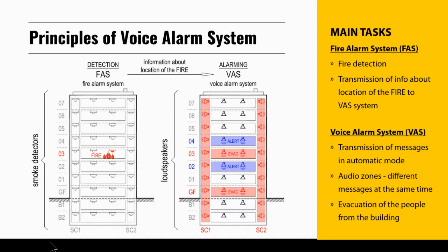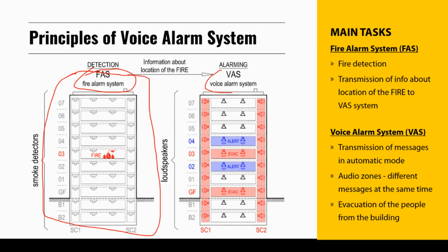Now, as you can see in this picture, one of the most common scenarios where we use a public address voice alarm system is the voice alarm system coupled with the fire detection system. Here on the left side we've got a building that has a fire alarm system. It's the same building on the left and the right side, but on the left we can see the fire detectors, and on the right we can see the voice alarm system endpoints, which are the loudspeakers.